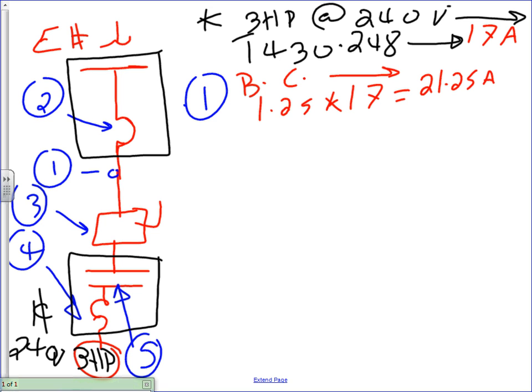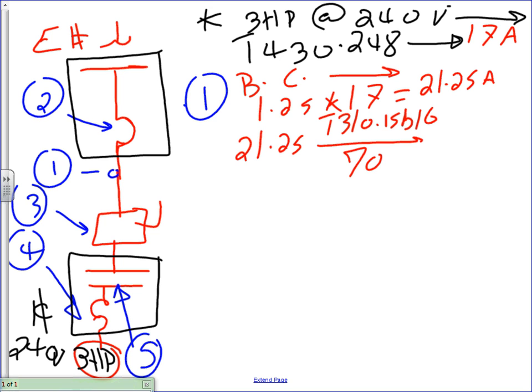Okay, then you're going to take the 21.25, you're going to take this one to Table 310.15(B)(16), under the 75 degree column. Under the 75 degree column, so if you guys go there, let's go size that boy. Everybody's there? 75 degree column. What's the conductor size I can get under the 75 degree column for this boy?